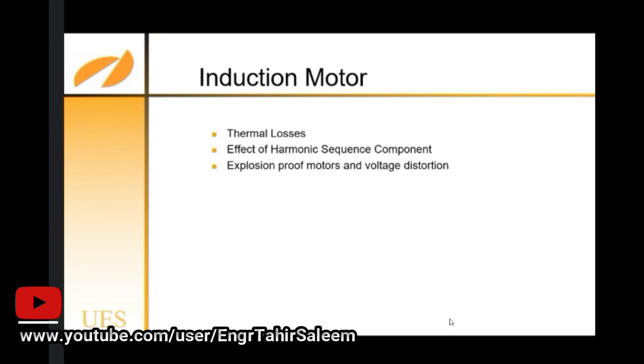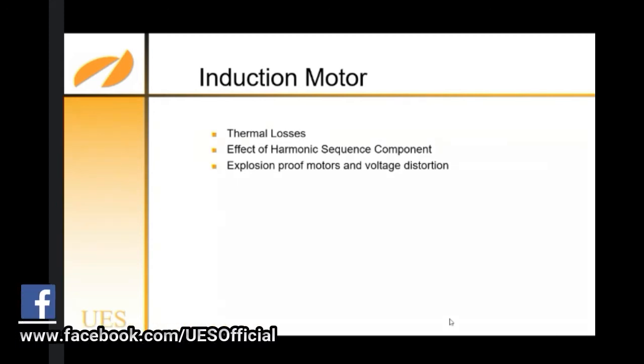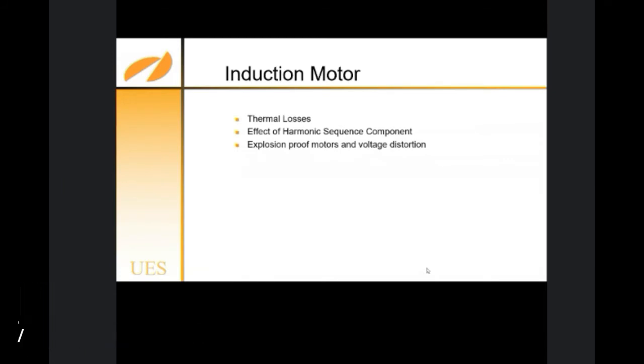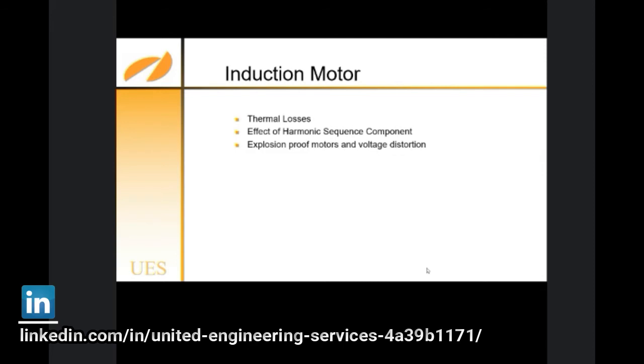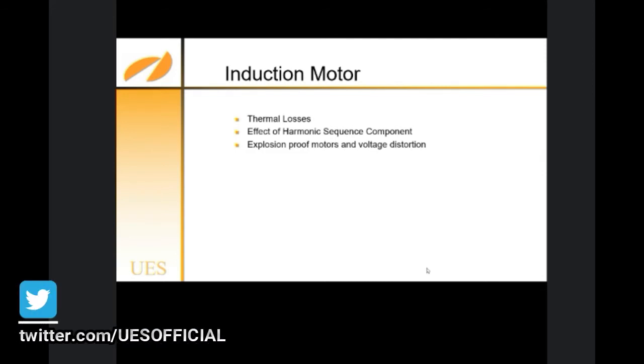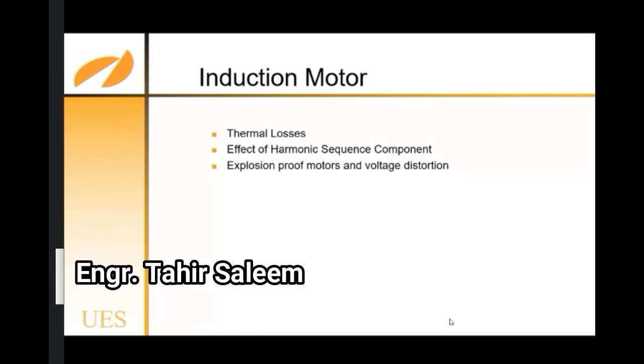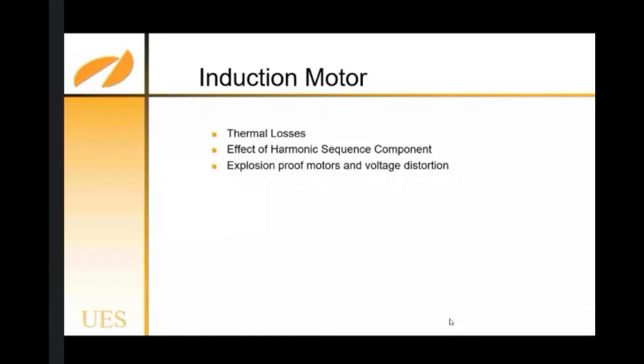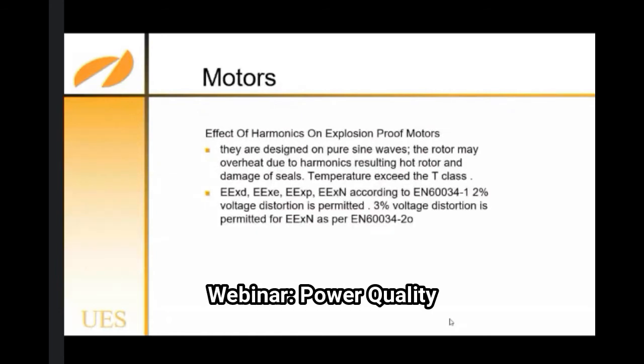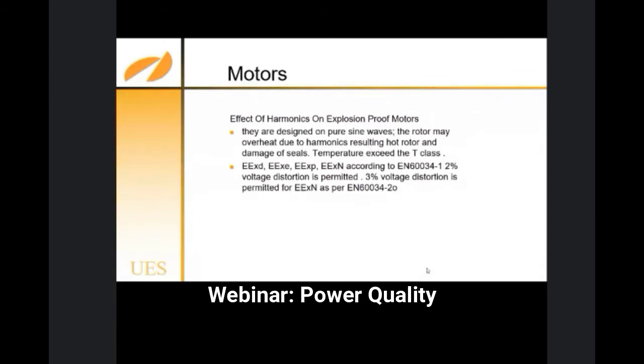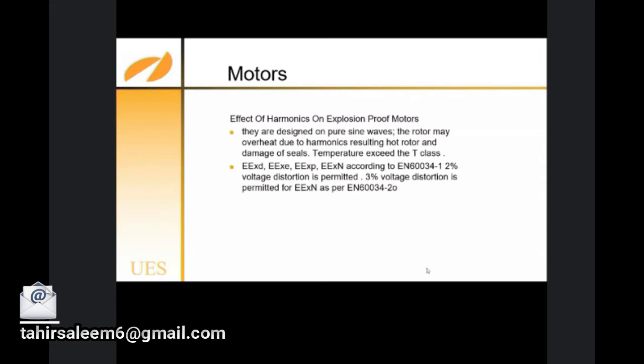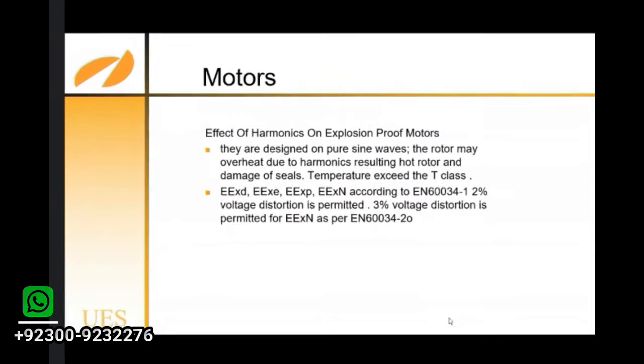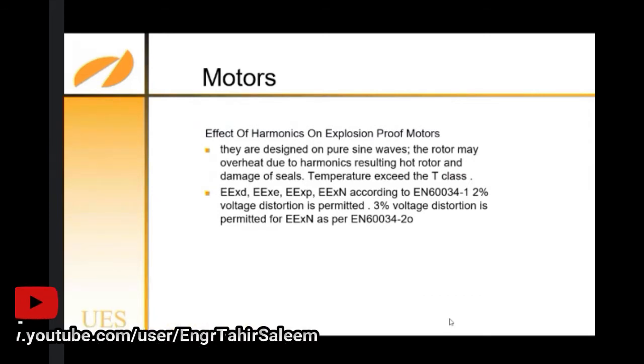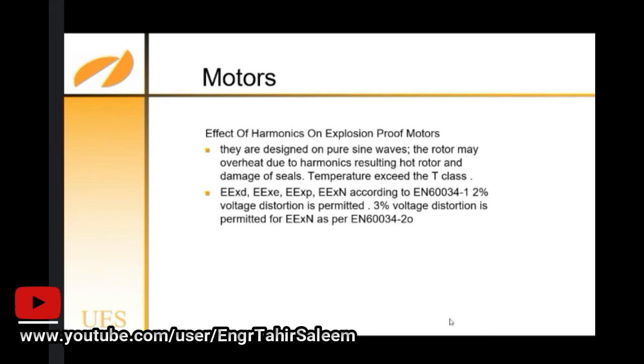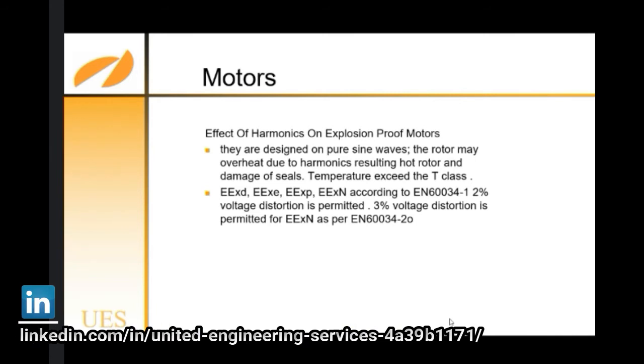Induction motor: thermal losses, effect of harmonic sequence components, explosion proof motors and voltage distortion. Harmonic sequence component means that if you are using a breaker, there's a point where the breaker should trip. The zero sequence changes, and this will trip the breaker. Again, as I explained earlier, explosion proof motors are designed for pure sine waves. The rotor may overheat due to harmonics, resulting in a hot rotor and damaged seals. Temperature exceeds the T class, which is T1 to T6. So these are the codes: according to EN 60034-1, 2% voltage distortion is permitted, and 3% voltage distortion is permitted for Ex n as per EN 60034-2.